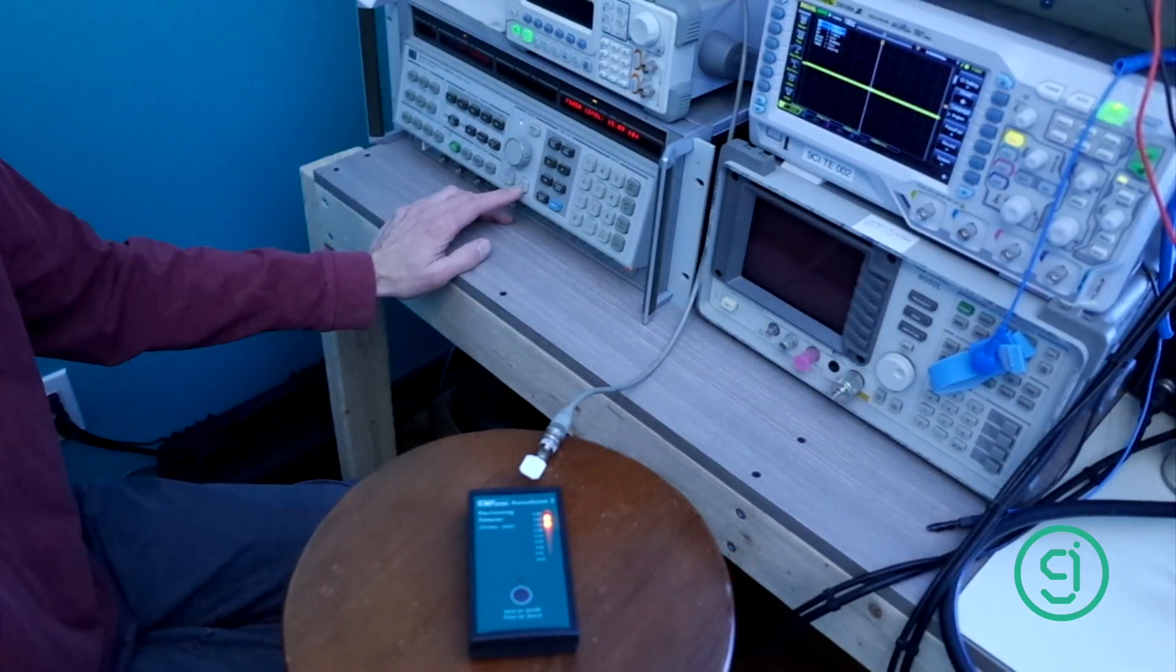-15 we're showing 0.1 volts per meter. -5 dBm we're showing 0.3 volts per meter. 5 dBm we're showing one volt per meter. +15 dBm we're showing somewhere between three and six volts per meter. So again, not super accurate for power.